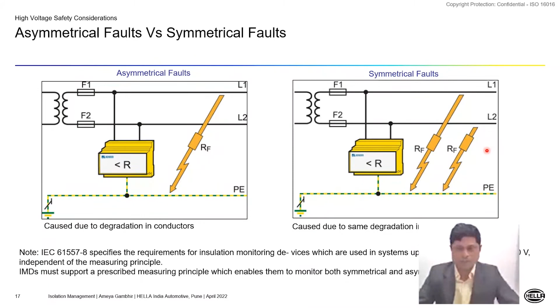Why I'm talking about this? Because this has a reference to some of the disadvantages of passive IMD systems that we are going to discuss in next slides. The IEC standard, which I mentioned before, is for IMD purpose only. It specifies that the requirements for insulation monitoring devices, it should support a prescribed measuring principle which enables them to monitor both symmetrical as well as asymmetrical faults. So even if both the leakage resistances are the same, the IMD must be able to detect that as a symmetrical fault scenario in an electric vehicle.